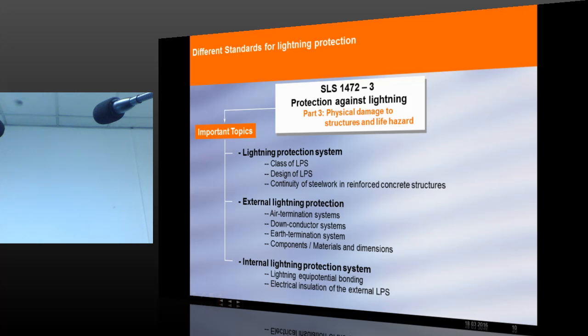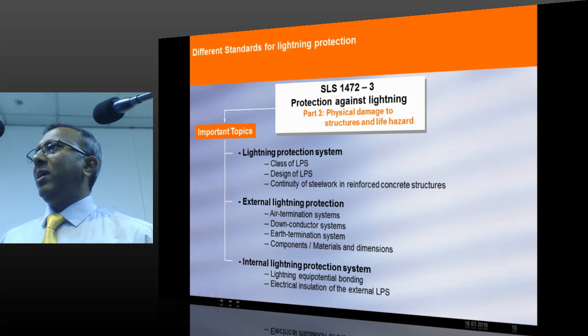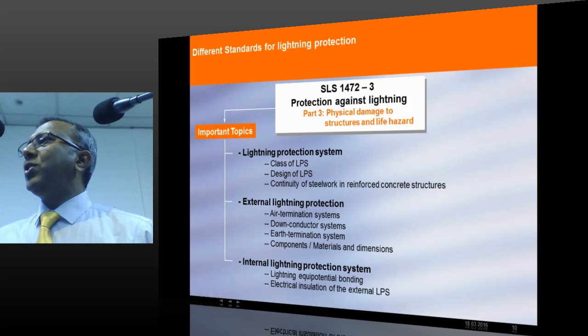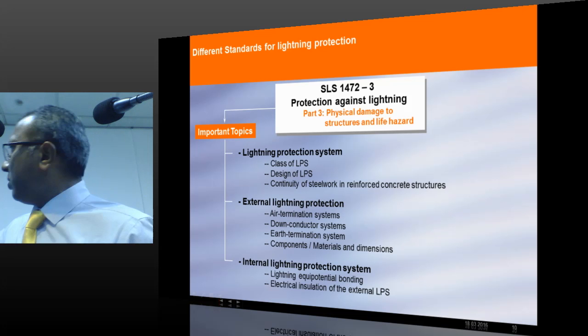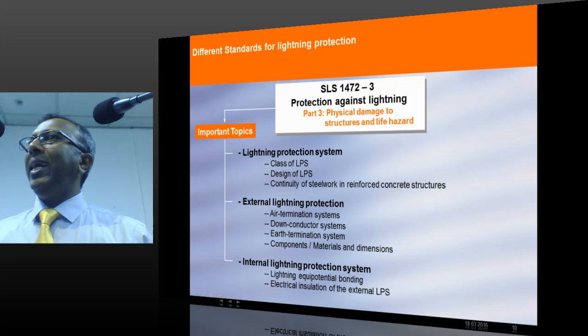Imagine that this is a chiller, and now we have put a rod here, which is connected to other parts of the building. How much distance is required to ensure that there is no flashover from the rod to the chiller is also explained in this particular standard. Various calculations are given, and if you want to have an exact, very good lightning protection system, each and every calculation needs to be performed.